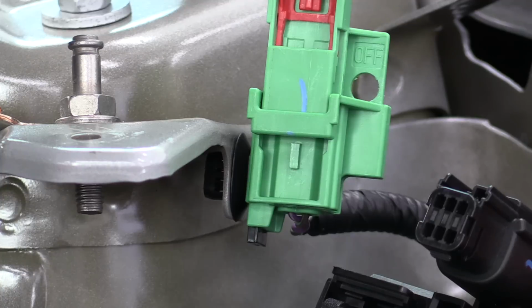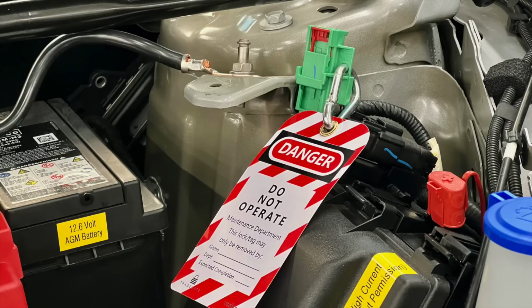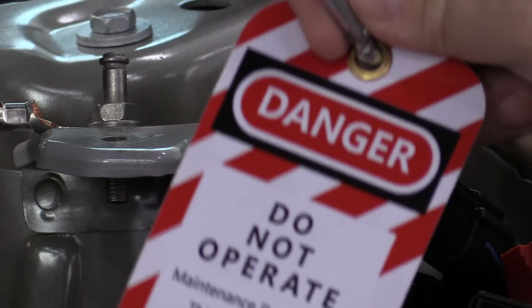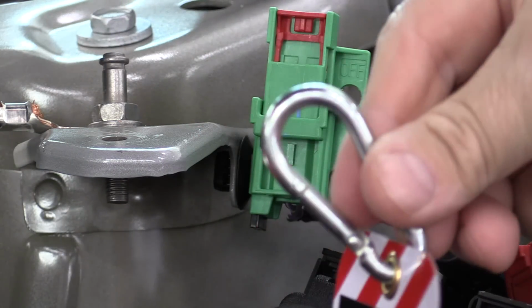Notice we have a hole right here, and the purpose of that hole is to put a do-not-operate tag on it. OSHA requirement 1910.147 for Lockout-Tagout requires that we come in with some sort of do-not-operate tag, preferably on a padlock. But in my classes, I'm not going to use the padlock - I'll use this carabiner or a zip tie.